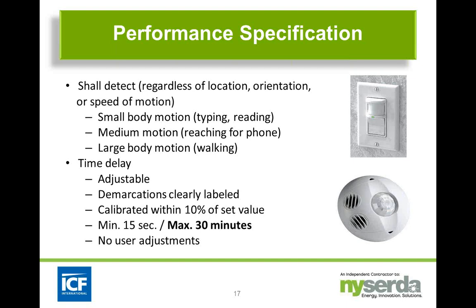Time delay, you need to be able to adjust the time delay. You want to make sure the demarcations are clearly marked. I'll actually show you some pictures in a few minutes of what some of these devices look like, of how you change the time delay settings, and some of them are kind of hard to understand. And you want to make sure that these are calibrated within 10% of the set values. Minimum shouldn't be any smaller than 15 seconds.